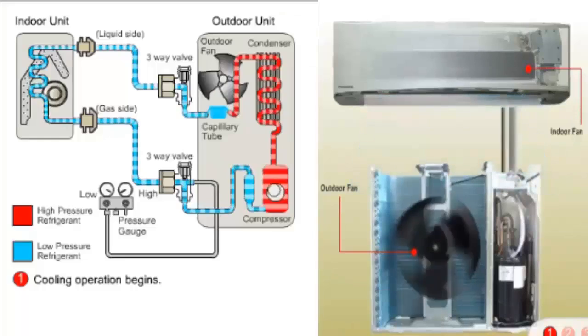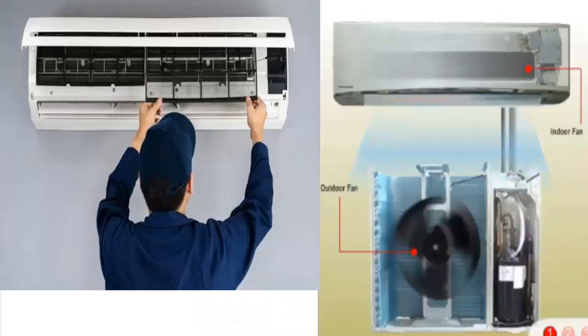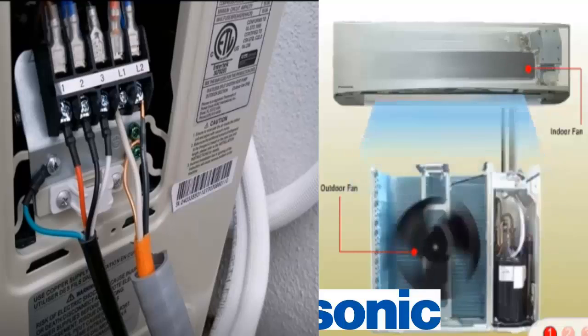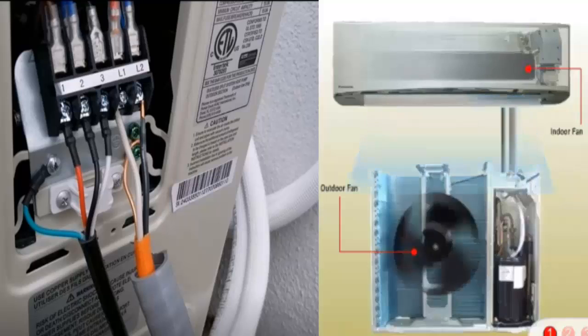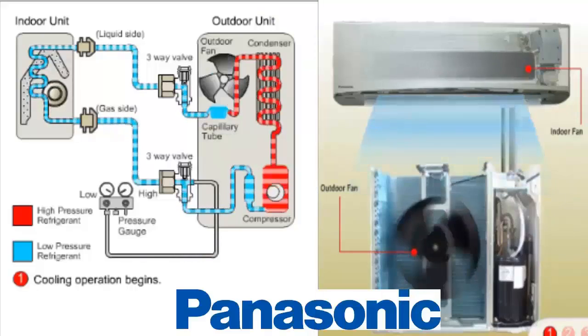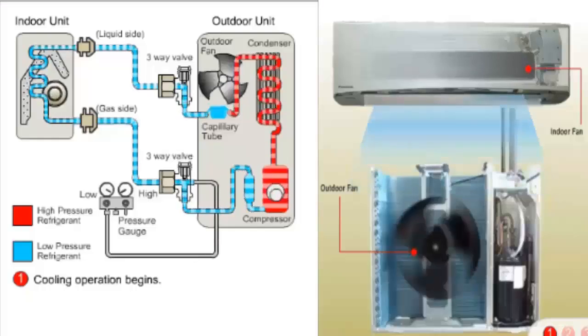Troubleshooting and solutions: Check the power supply, ensuring it is within the specified values by the manufacturer. Verify internal wiring, the distribution board, and circuit protection to ensure proper voltage. Conduct a visual inspection of the outdoor unit, especially the condenser — ensure it is clean, without obstructions, and that the fan is functioning correctly. A dirty or obstructed condenser can cause overpressure problems.